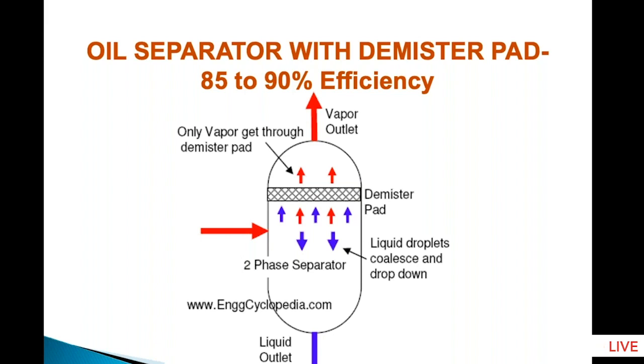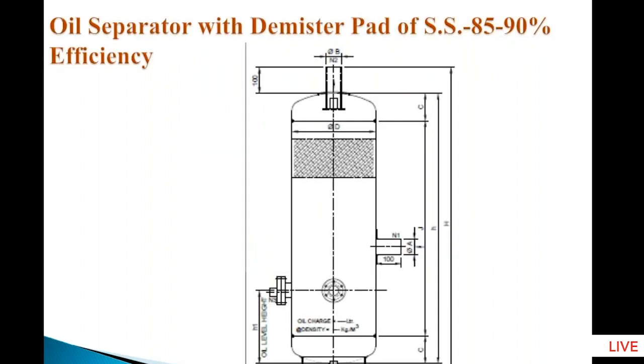So the demister pad is a stainless steel pad which traps the oil. The oil falls down, liquid droplets coalesce and drop down, and only vapor is sucked by the compressor. So this is a more efficient oil separator, and I would recommend that you use this kind of oil separator rather than only a gravity separation oil separator. The third oil separator is also very efficient, 85 to 90% efficient. There is a stainless steel demister pad, as you can see, built inside the oil separator. This design is available in India.